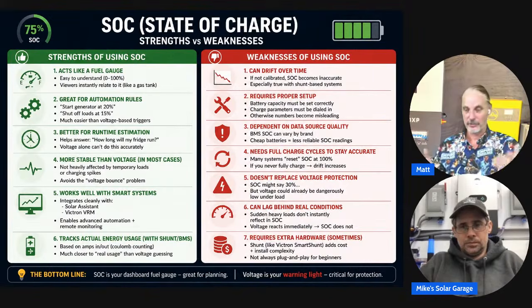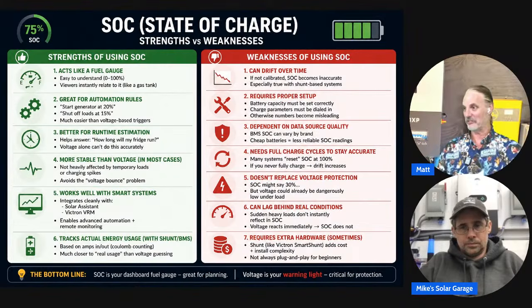I said, okay, in order to make sure everything's running, I want to get it into a nice stress test to get everything running, so I can check amperages on all the wires, put a heat gun on them, and double check everything's doing what we think. We pull it up and it's running at 108 amps. I'm thinking, okay, I got a good pull here - he's got every device in his facility turned on. I push the amp meter over the main line and it says 108, matching his shunt.